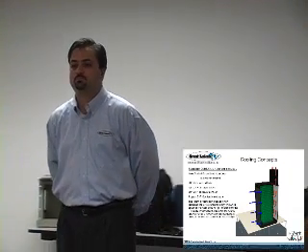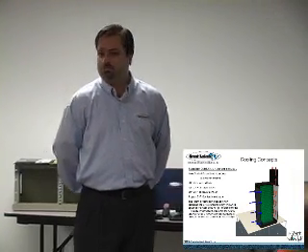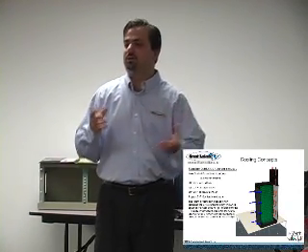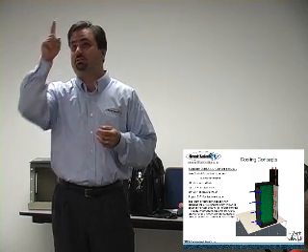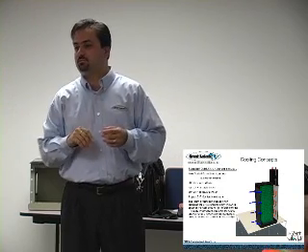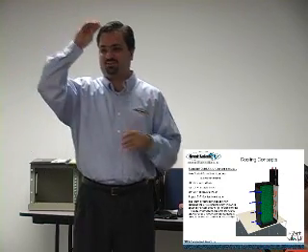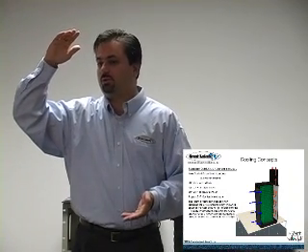You're actually ducting that out of the room all the way? Completely ducted out of the room. That's expensive. It depends on the methods. If you duct each one with the traditional HVAC, or I've seen people actually have it ducted just into the drop ceiling, and the intake is actually from that. So they're using the raised floor and the drop ceiling both as hot and cold pressure points.